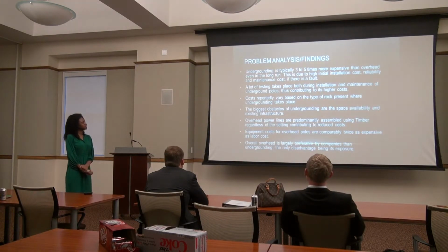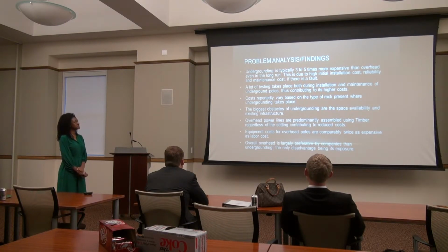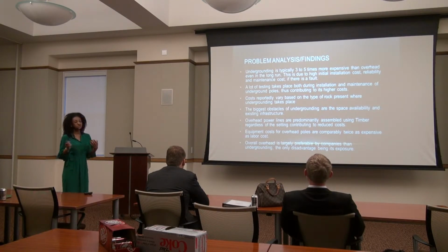So the problem analysis and findings I could come up with were that typically it's more expensive to bury transmission lines than to have them overhead. And the reason is because of the initial cost, which is the cost of installation, and also in the long run, due to reliability and maintenance. If there's any sort of fault, because it's buried, you have to excavate the whole thing again and test and all that. It's so much more expensive.